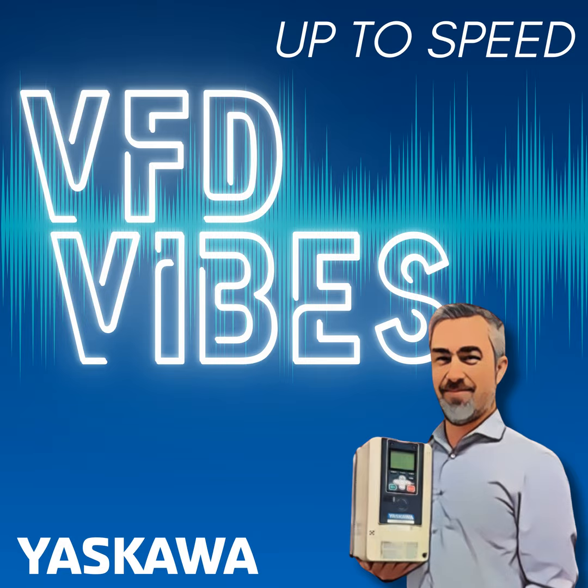What do I mean by that? A 10 horsepower motor, NEC amps, at 460 volt is generally 14 amps or less. And that's what our drives are rated to. A 10 horsepower VFD 460 volt would be rated for 14 amps output current. If you get into a certain situation, maybe a specialty application where it's a high pole count motor, high torque, it may have a higher amperage. It might have a 10 horsepower rating, but it might pull 15 or 16 amps full load. If that were the case, you'd want to upsize your drive.